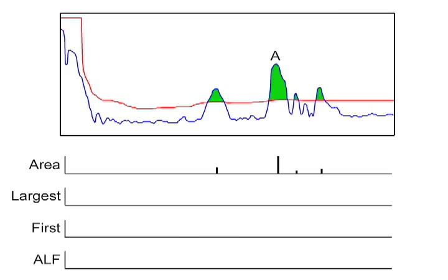The second component is the large component. The echo with the largest height above the TVT curve will be given the highest score. Again, it is our second echo. The first component is next. The echo that comes first is given the highest score. All of the component scores are totaled and the echo with the highest total score is determined to be the true material echo.